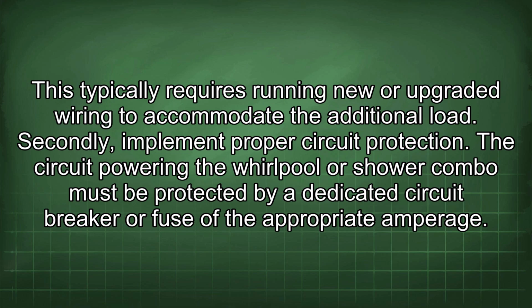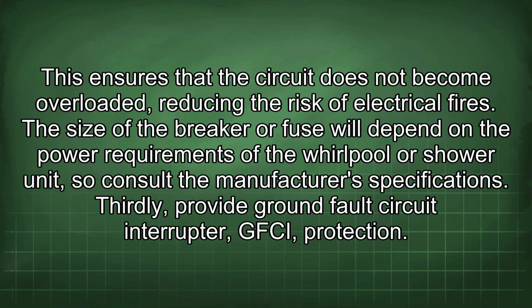Secondly, implement proper circuit protection. The circuit powering the whirlpool or shower combo must be protected by a dedicated circuit breaker or fuse of the appropriate amperage. This ensures that the circuit does not become overloaded, reducing the risk of electrical fires. The size of the breaker or fuse will depend on the power requirements of the whirlpool or shower unit, so consult the manufacturer's specifications. Thirdly, provide ground fault circuit interrupter (GFCI) protection.